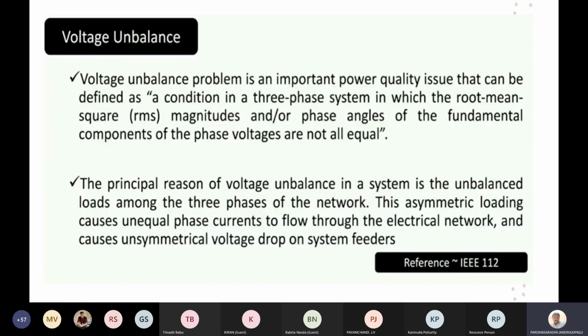One more thing we have is unbalance, which you can generally find in a three-phase system. Voltage unbalance is an important power quality issue that can be defined as a condition in a three-phase system in which the root mean square magnitudes and phase angles of the fundamental component of the phase voltage are not equal. Here we are expecting all the phases to be properly balanced. Otherwise, if the magnitude or phase angle varies from one phase to another, it comes under voltage unbalance. The principal reason for voltage unbalance in a system is unbalanced loads. This asymmetric loading causes unequal phase currents to flow through the electrical network and causes unsymmetrical voltage drop on system feeders. All of this we are discussing according to the IEEE standard only.